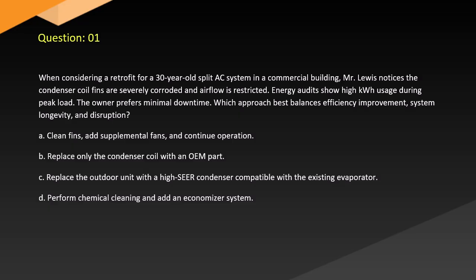Question 1. When considering a retrofit for a 30-year-old split AC system in a commercial building, Mr. Lewis notices the condenser coil fins are severely corroded and airflow is restricted. Energy audits show high usage during peak load. The owner prefers minimal downtime. Which approach best balances efficiency improvement, system longevity, and disruption?